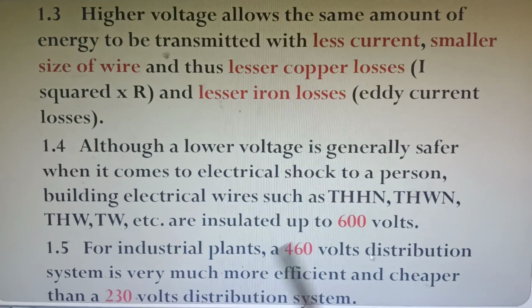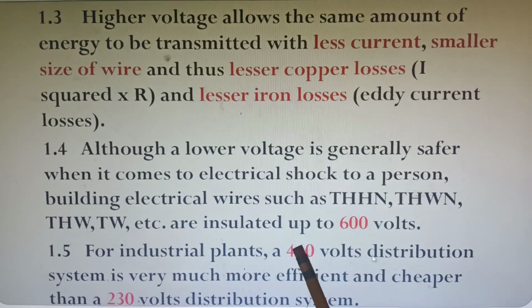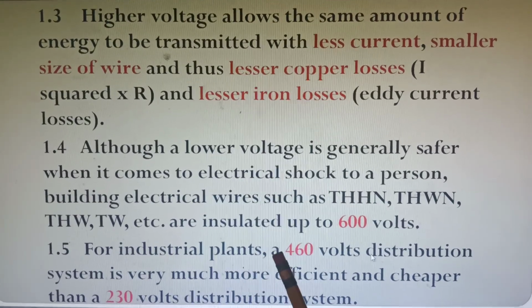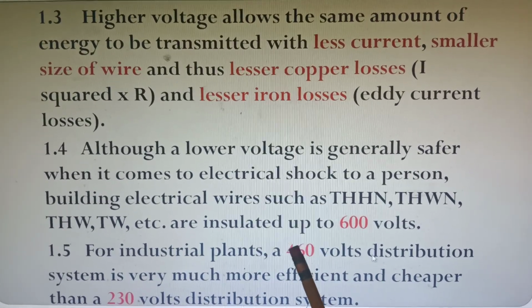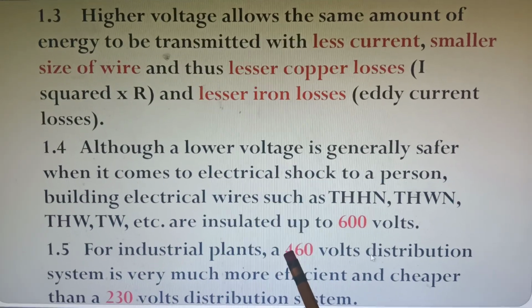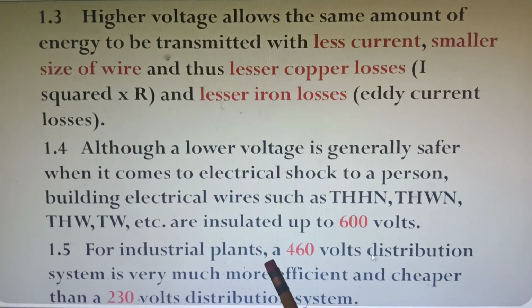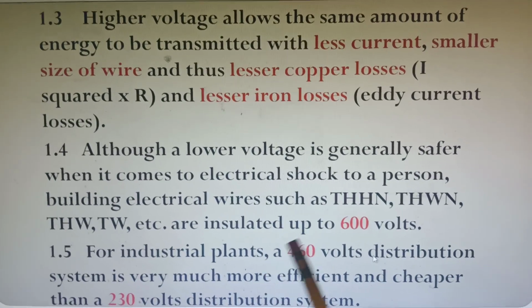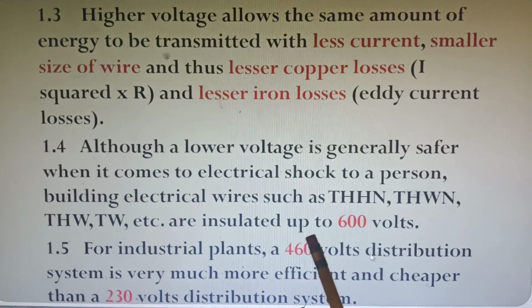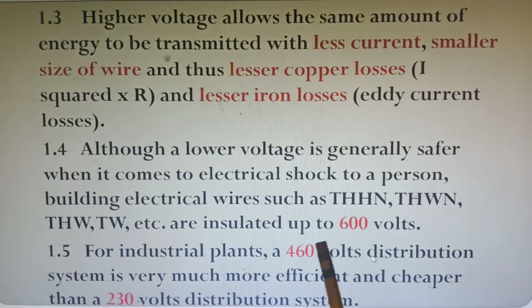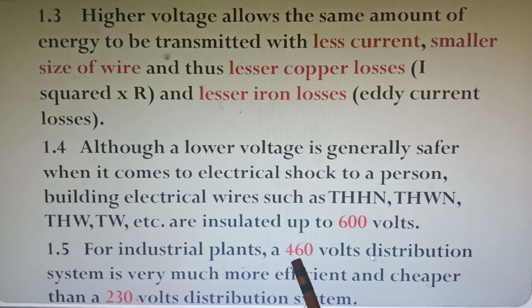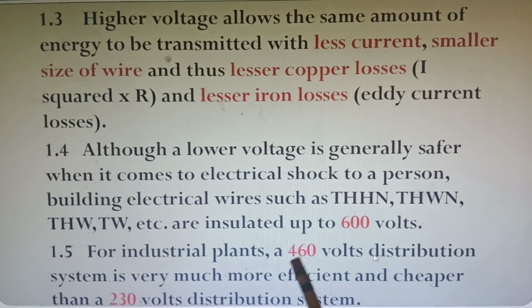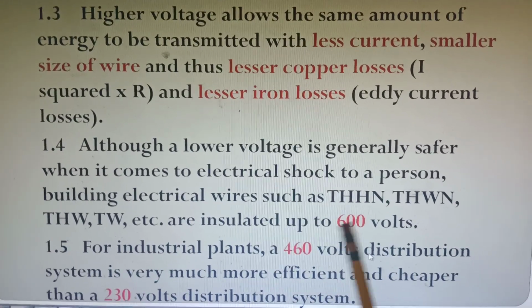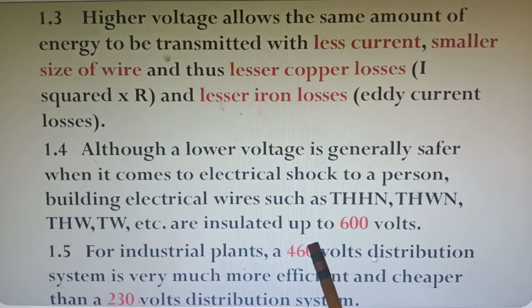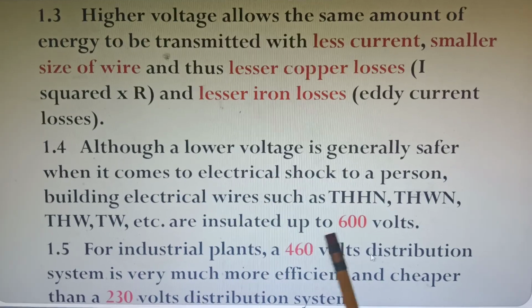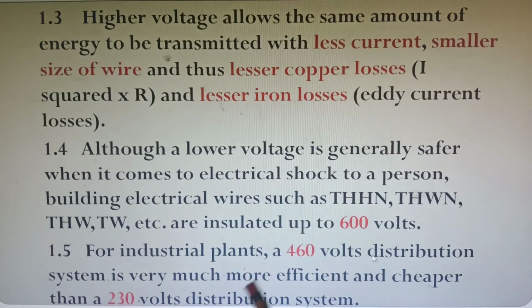The wires are no problem, you can reuse them because with a higher voltage the currents become smaller. But you'll have problems with the magnetic controllers, which are rated 230 volts. So when you upgrade to 460 volts, there's a need to change many of the control transformers and the holding coils of the magnetic starters. That's a lot of work. There should be a need to evaluate the cost of upgrading from 230 to 460 volts versus the savings.